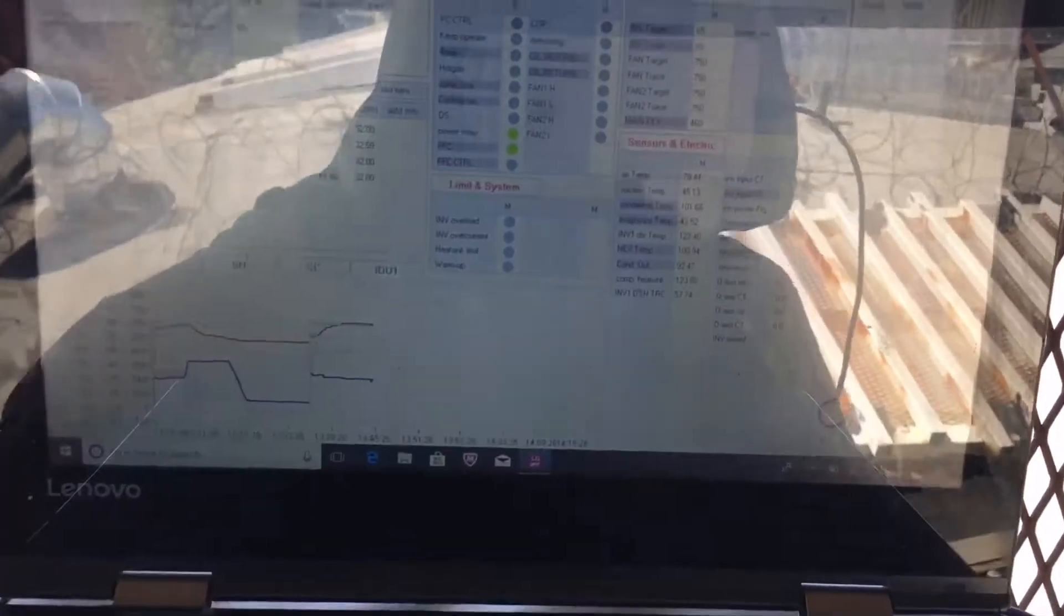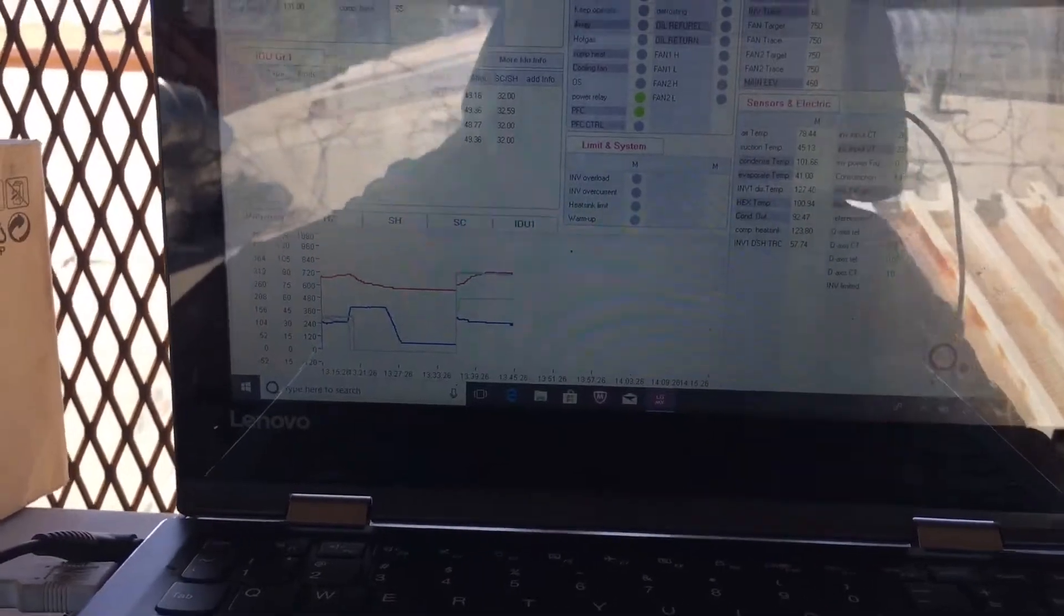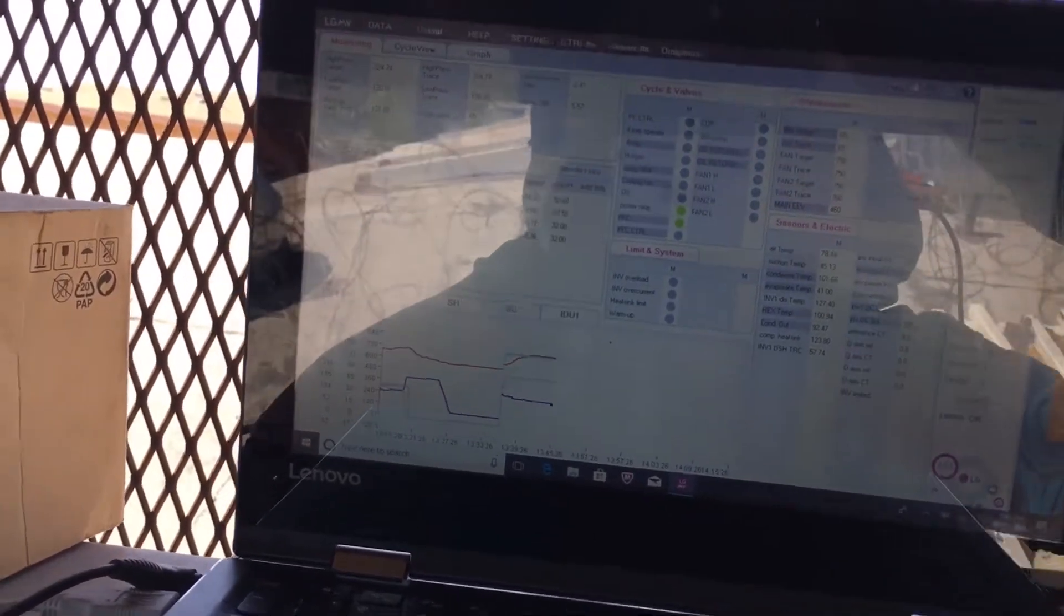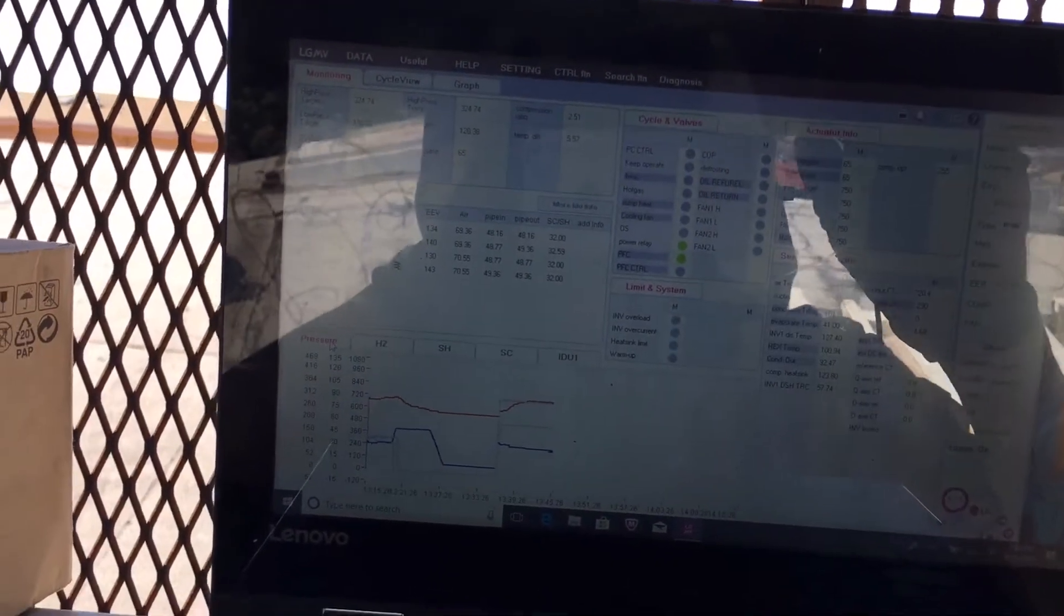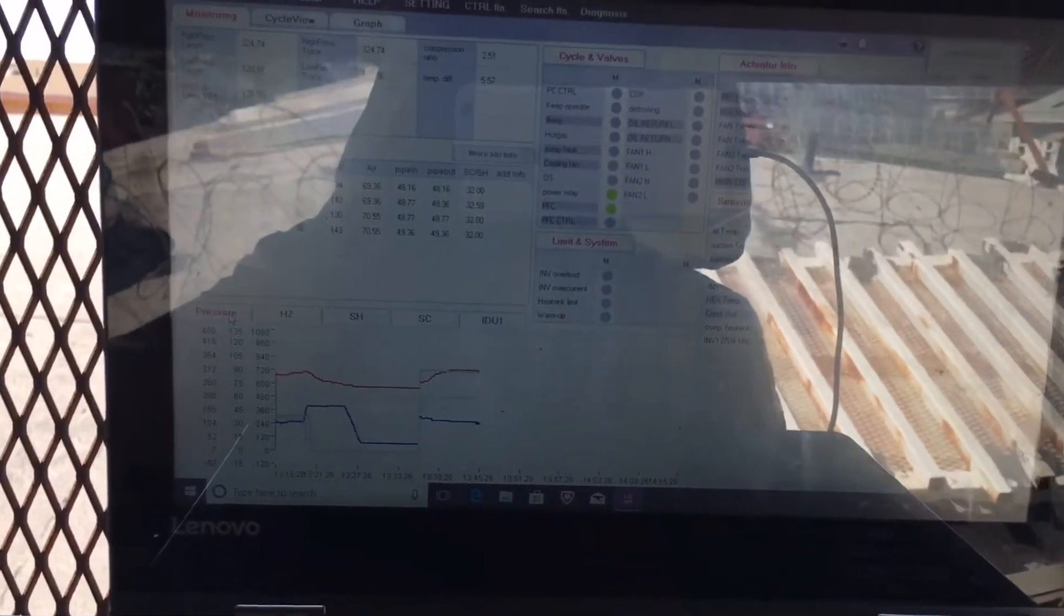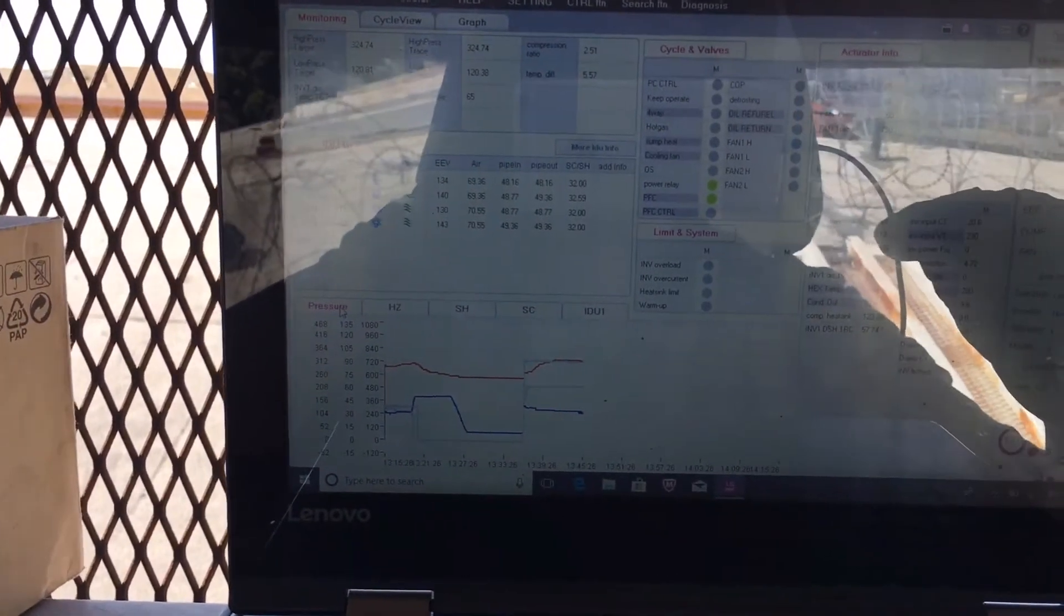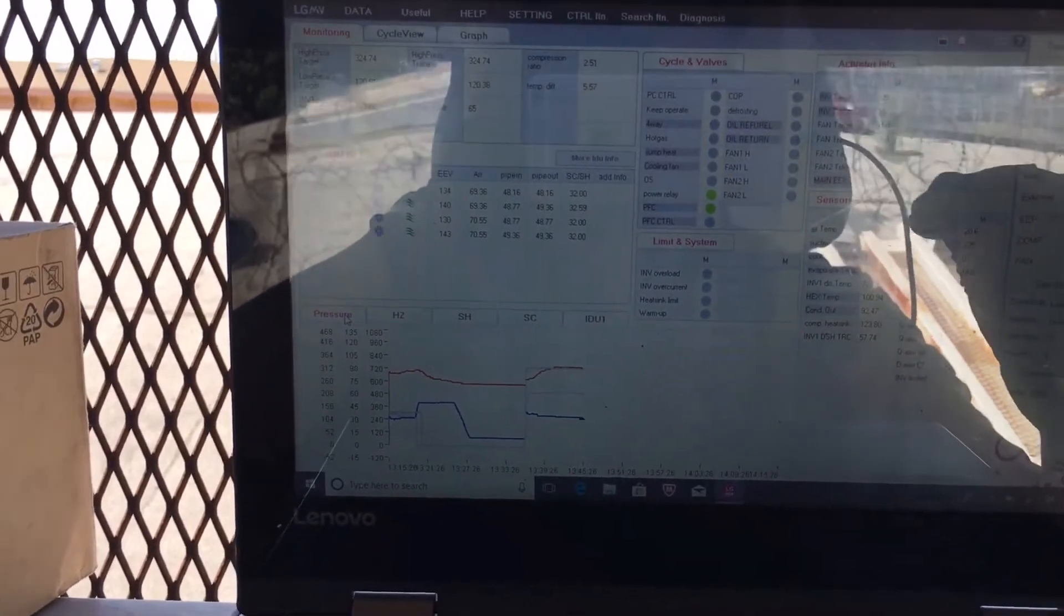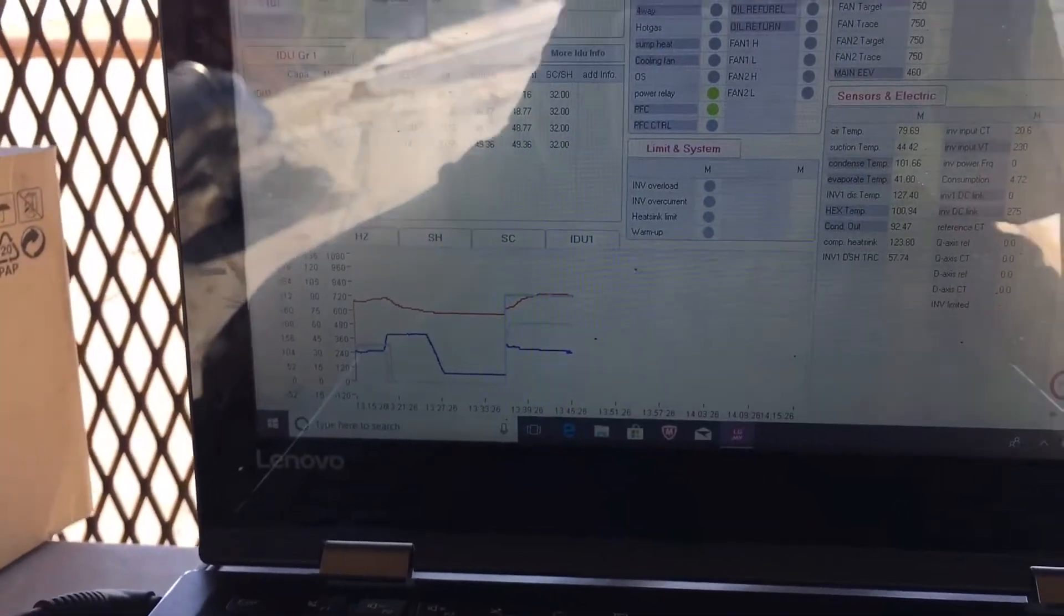When you're going to take superheat and subcool and test these systems, you put the system in its software and hardware into a test mode. When it's in test mode, it will set the outdoor fans, the compressor speed, the indoor fans to a set program that it knows it needs to meet to actually do its test parameters.